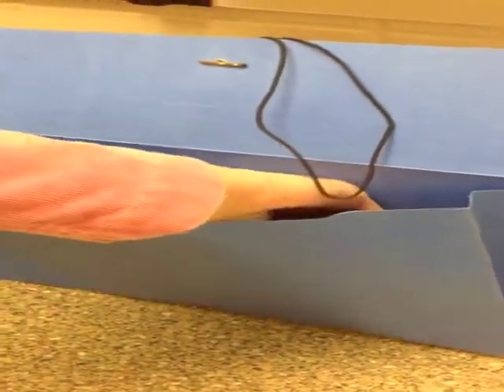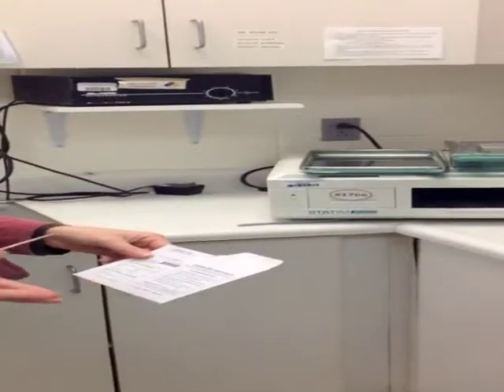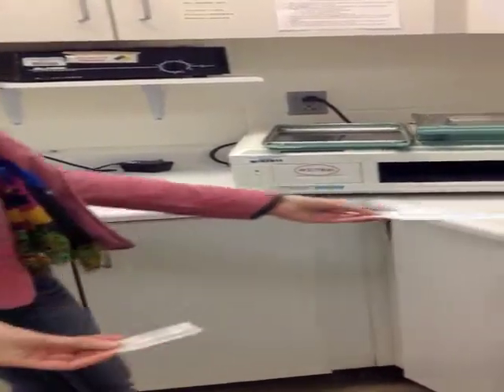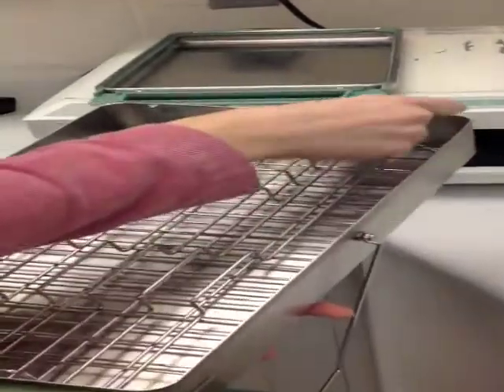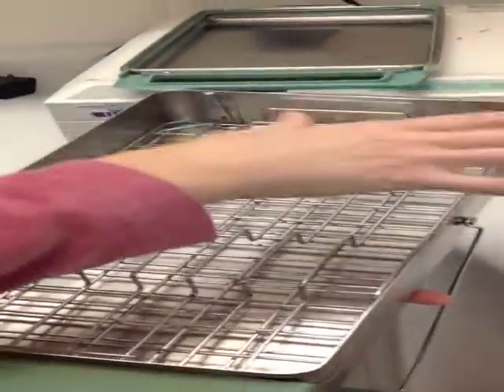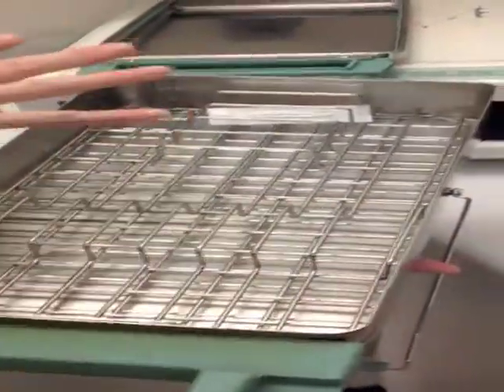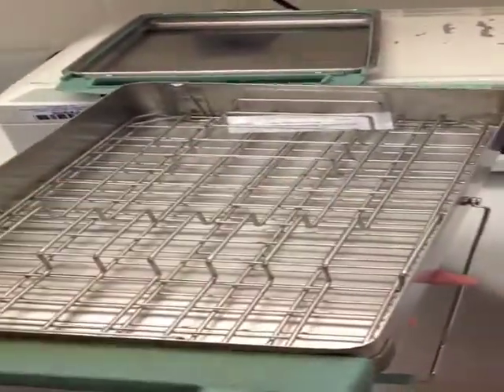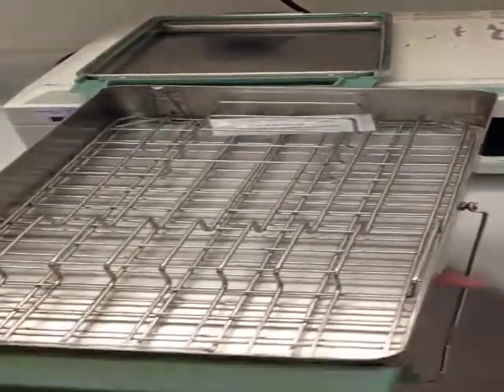So we will open up this container, and inside the folder is our spore test. We have to open up the envelope to actually find the test strip. This is the test strip that we will use. When spore testing the Statim, we're going to remove the spore strip from the envelope. We will load the Statim with instruments, but when you place the spore test, you want to make sure you place it in the back of whatever container you're going to use when you're sterilizing. You want to place it in the back of the container because we want to make sure that the steam wraps around all of the instruments.